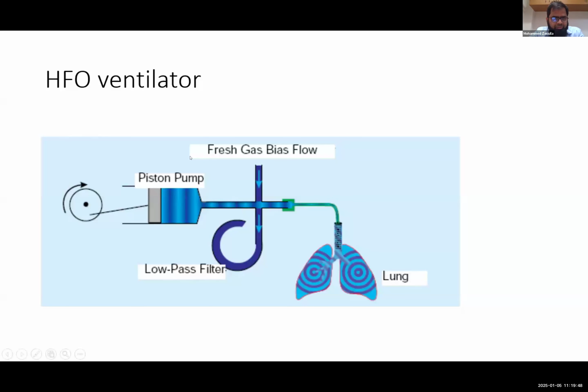In addition to that, you will set FiO2 and mean airway pressure. And in a high frequency ventilator, the bias flow is also very high. In conventional ventilation you will use 10 to 12 liters, but here you have to use a very high bias flow, around 30 to 40 liters per minute. So you should have proper humidification whenever you are giving high frequency ventilation.